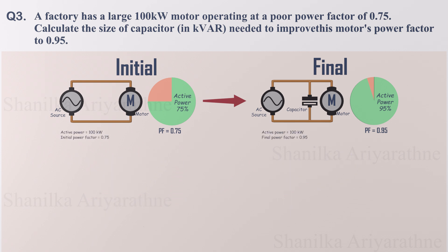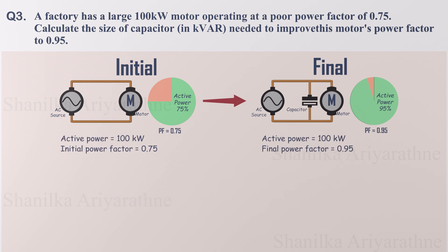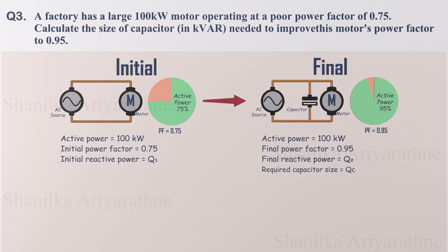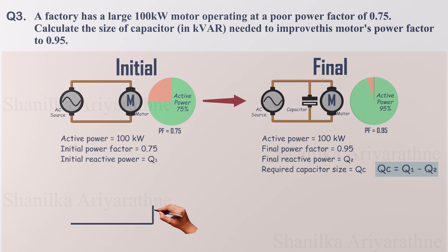So how do we find the perfect capacitor size? Here's our plan: if the initial reactive power is Q1 and the final reactive power is Q2, the size of the capacitor's reactive power we need, QC, will be equal to Q1 minus Q2. So we have to find the reactive values Q1 and Q2. To find the reactive powers, there are several methods — let's draw the power triangles.